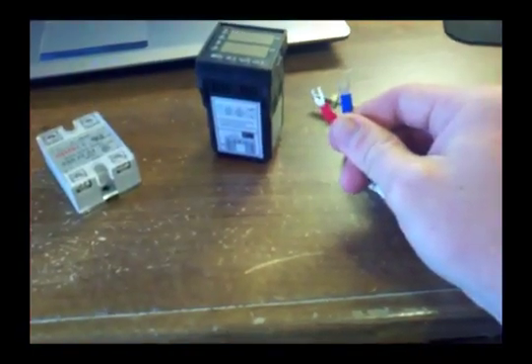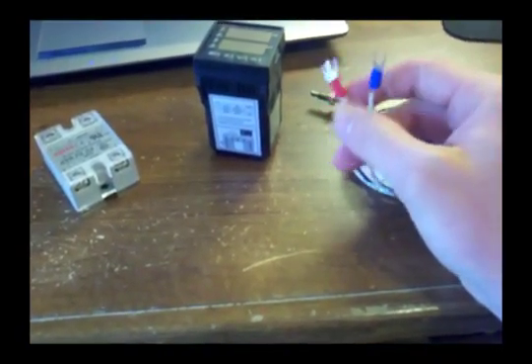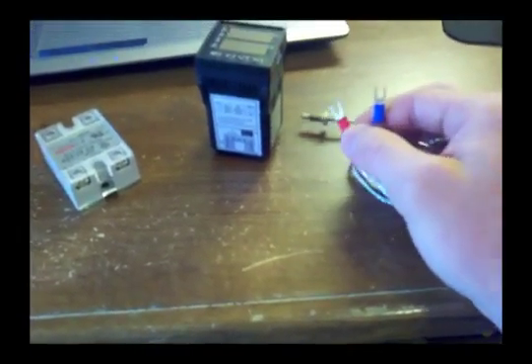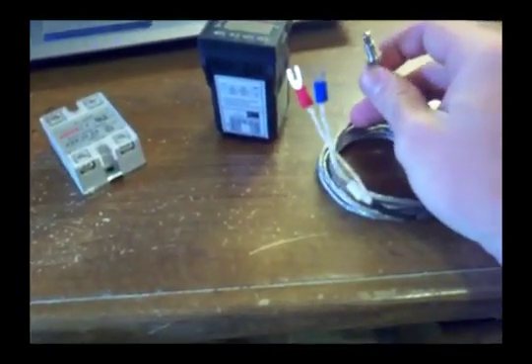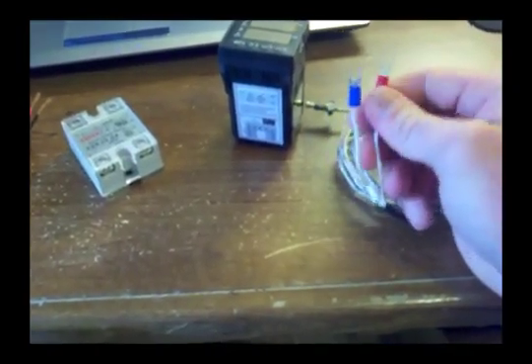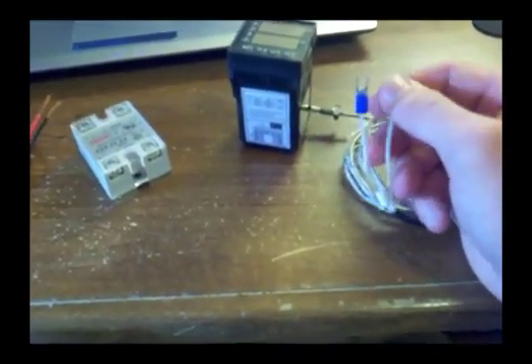Like, for instance, which one of these is positive and which one's negative? I found a website that said that the industry standard for thermocouples was that the red was negative. So I wired it up that way, and when I put the end of the thermocouple in my refrigerator, instead of the temperature reading going down, the temperature reading was going up. So I said, okay, so I tried it the other way, and I put the blue on the negative terminal and the red on the positive terminal, and then it was going in the right direction.